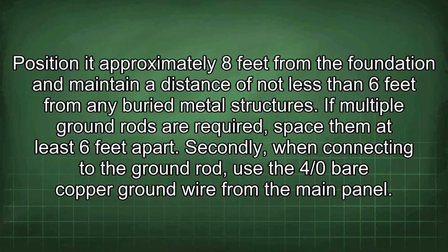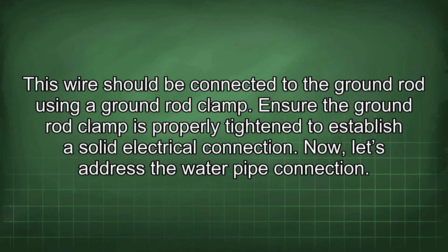from any buried metal structures. If multiple ground rods are required, space them at least 6 feet apart. Secondly, when connecting to the ground rod, use the 4/0 bare copper ground wire from the main panel. This wire should be connected to the ground rod using a ground rod clamp. Ensure the ground rod clamp is properly tightened to establish a solid electrical connection.